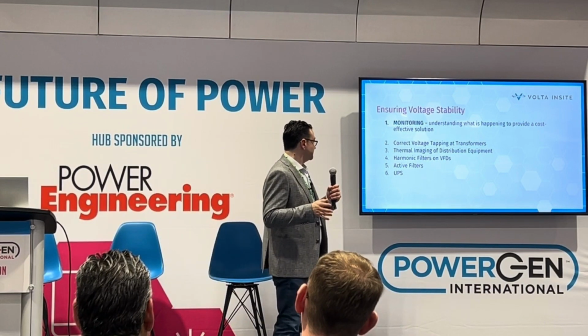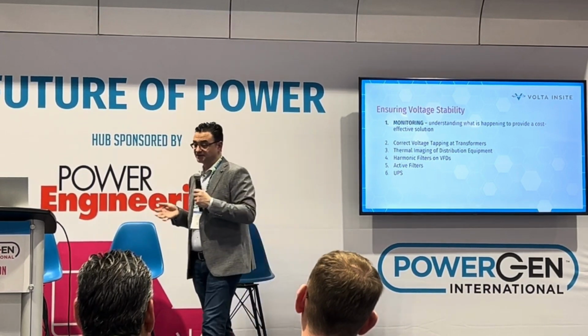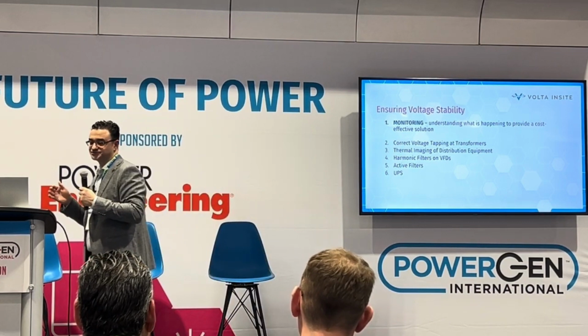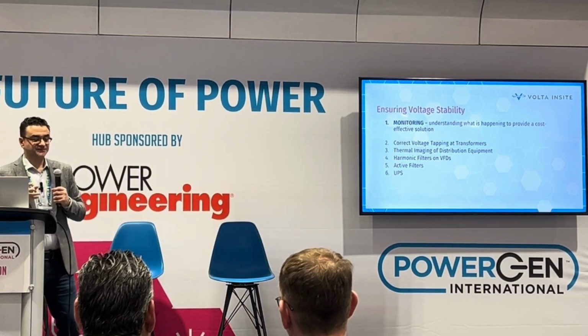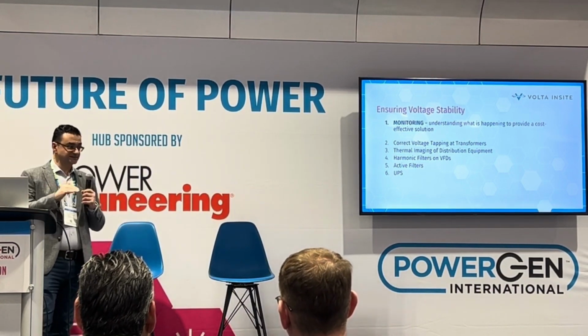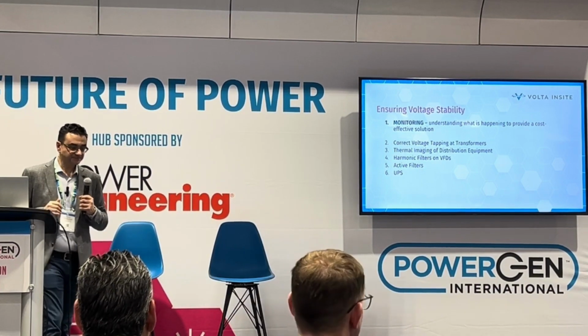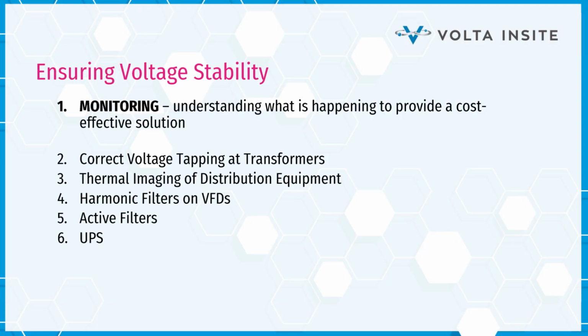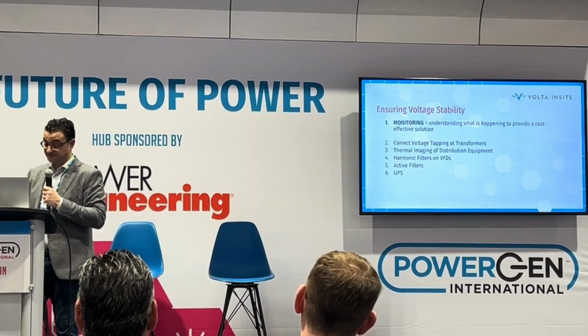Furthermore, on voltage stability within a facility, once you have data, you can ensure that your transformer voltage taps are set accordingly to maintain the proper voltage levels. Additionally, on the predictive maintenance side, you can do some level of thermal imaging on your distribution equipment, which will isolate hotspots. And then you can add harmonic filters on VFDs, active filters, and ultimately, if you're really concerned about voltage variations, a UPS, which is very expensive.